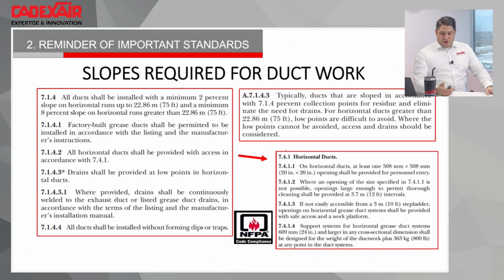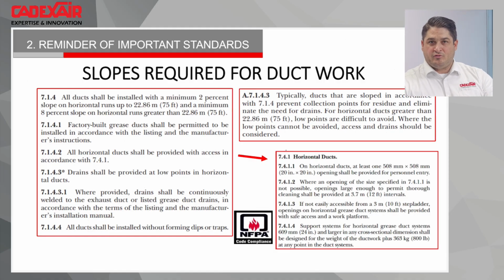Okay, thank you. Yeah, this one is the favorite of all the mechanical engineers and contractors, and it's still something not new, but from the 2015 version. Now there's a slope asked for in the ductwork. So technically, all horizontal ductwork less than 75 feet needs to have a 2% slope. And if it's more than 75 feet, they will ask for 8%. So just to bring that to everybody's mind, we will jump directly to 100 feet of ductwork.